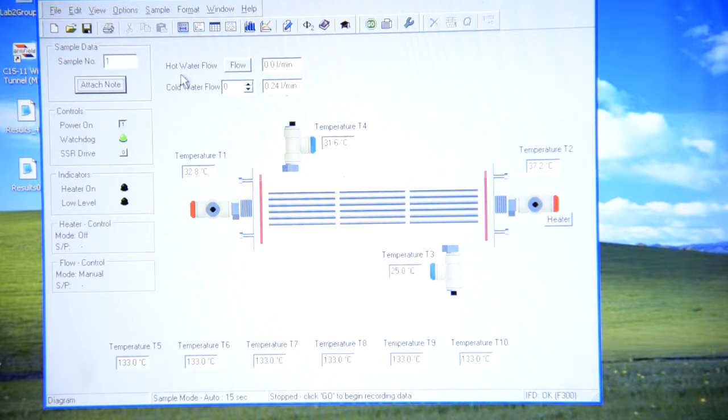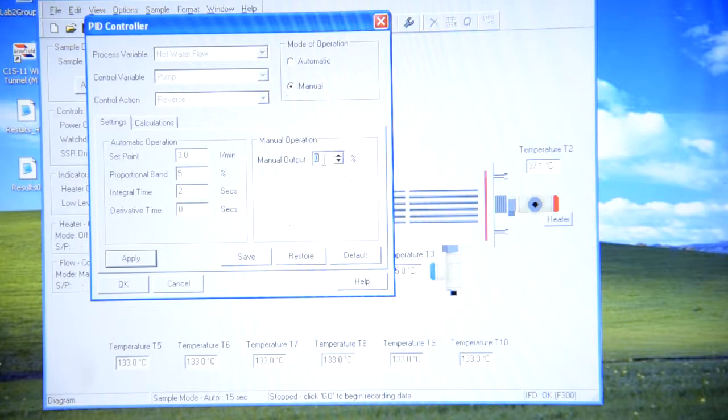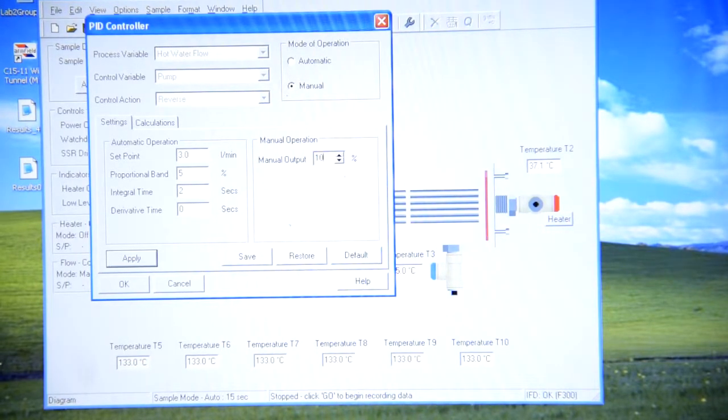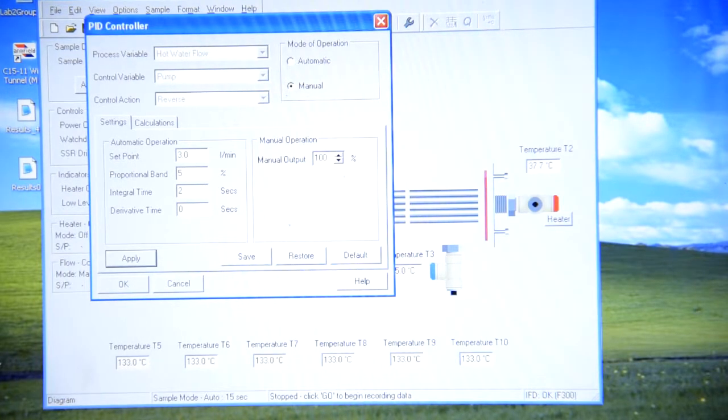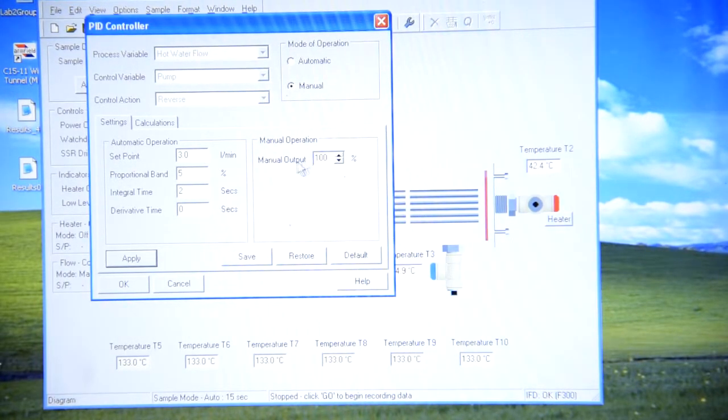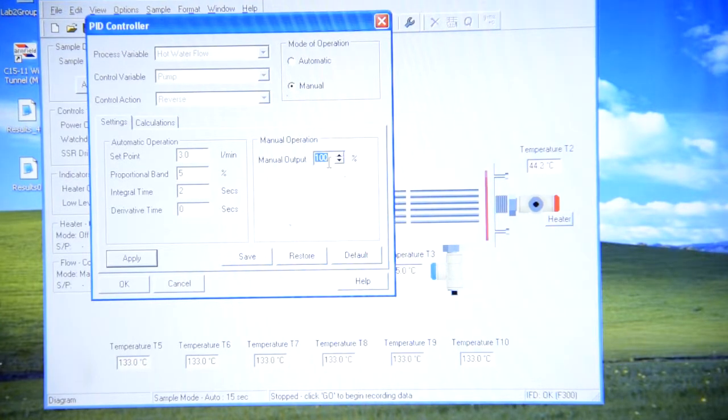Then you should select hot water flow, select manual mode, and input something like 100%. After this, the pump should be working. Then, after checking, you can put zero again.